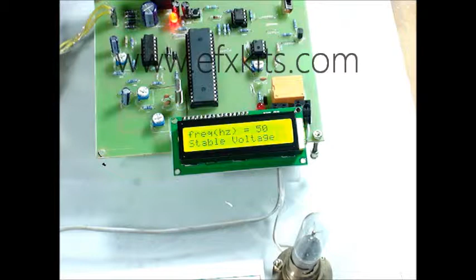This is model number 64, developing islanding arrangement automatically for grid on sensing bad voltage or frequency. This is particularly to connect one more source of supply, could be a solar with an inverter, to the grid. But connecting to the grid, one must ensure that the frequency is maintained and the voltage is also maintained apart from the phase.